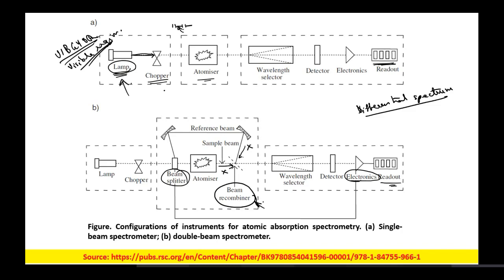In the first case, we have a lamp and a chopper. The chopper has an on time during which light passes through and interacts with the sample. After that, the chopper stops the lamp light from entering the sample chamber, and during that time the readout happens.